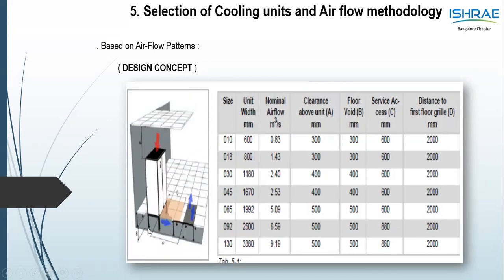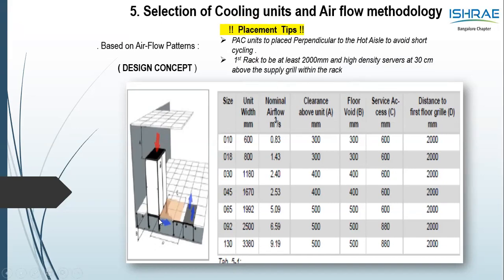Not only that, even the false floor height has to be maintained at a specific minimum height. Otherwise, too high a space would have an air loss issue. So a minimum recommended height is also given, and the service. All the service happens from the front of the unit, so sufficient space is to be maintained based on the CFM or the capacity of the unit. Also, a quick tip for all of you is that all these units have high airflow, as I said, 500, 600, 650 CFM per ton. So it's recommended to place the rack at least 2000 mm from the PAC units, and the CCU units will be placed perpendicular to the hot aisle so that you have sufficient flow of the hot air and sufficient flow of cold air to the rack and server.